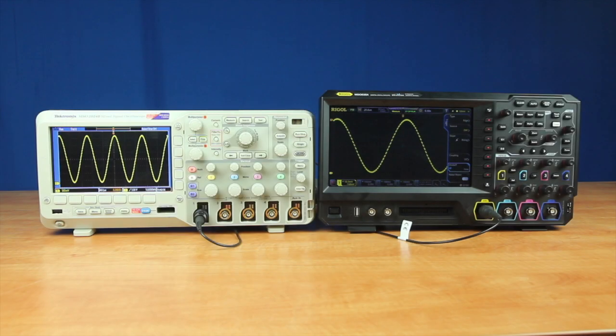Let's compare the storage capabilities of the Rigol MSO5000 series against the Tektronix MSO2000B series. Both instruments are recently calibrated, and the Tektronix is running firmware version 1.56. Let's start by capturing a CSV file from the Tektronix MSO2000B series.